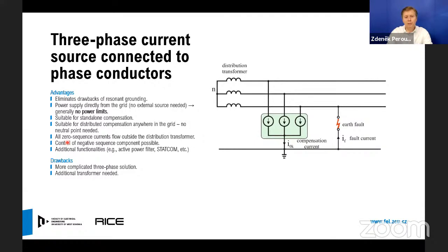That's a configuration which I love, and that's the configuration when the active current source is connected between the phase conductors of the grid and the ground. It eliminates the drawbacks of resonant grounding. We can take the active power necessary for the operation of the device directly from the power grid, so we do not need any external source. And generally, we have no power limits in this configuration.